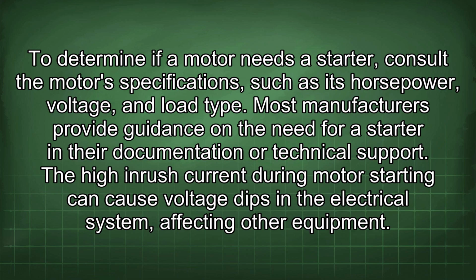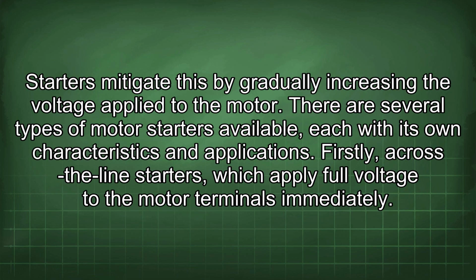The high inrush current during motor starting can cause voltage dips in the electrical system, affecting other equipment. Starters mitigate this by gradually increasing the voltage applied to the motor. There are several types of motor starters available, each with its own characteristics and applications.